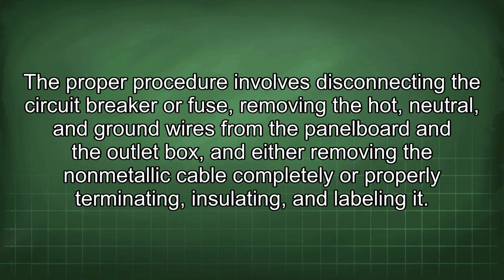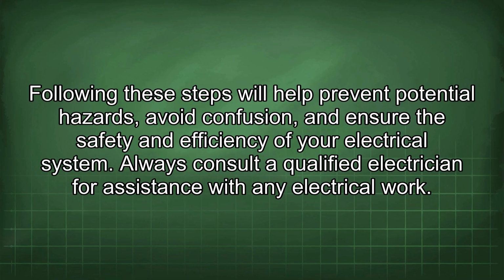The proper procedure involves disconnecting the circuit breaker or fuse, removing the hot, neutral, and ground wires from the panel board and the outlet box, and either removing the non-metallic cable completely or properly terminating, insulating, and labeling it. Following these steps will help prevent potential hazards, avoid confusion, and ensure the safety and efficiency of your electrical system. Always consult a qualified electrician for assistance with any electrical work.